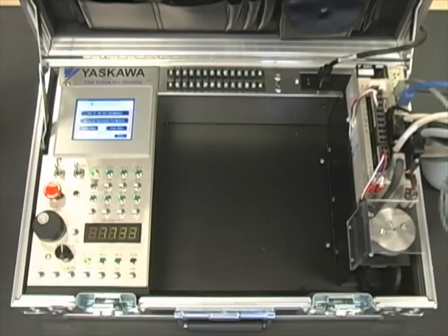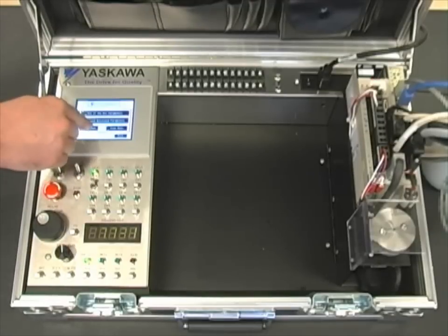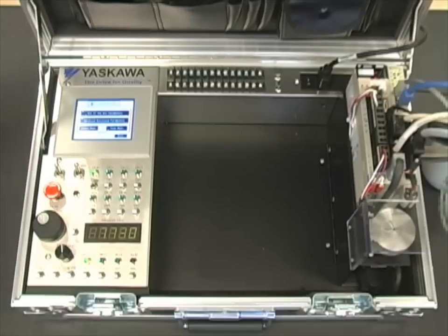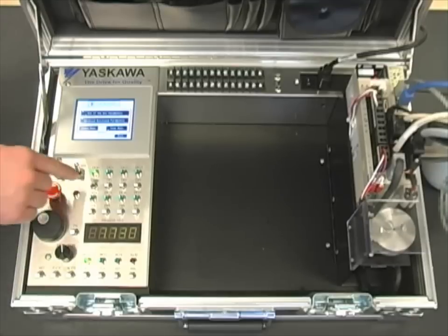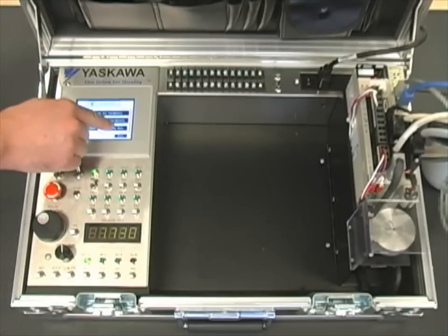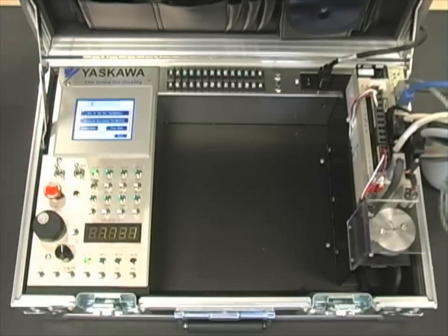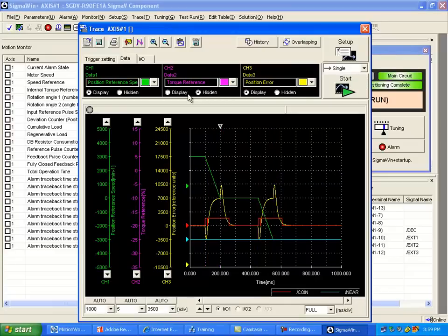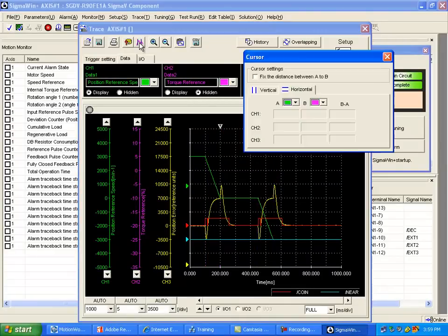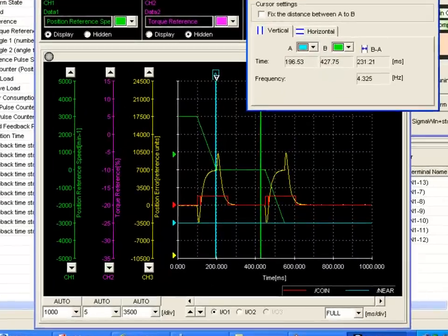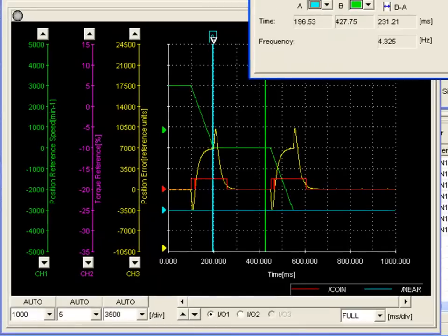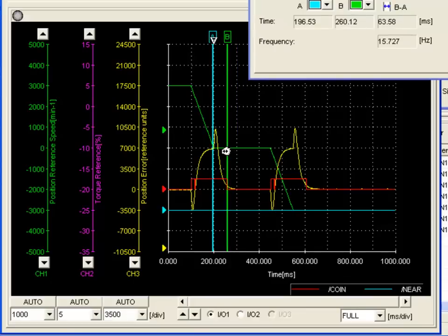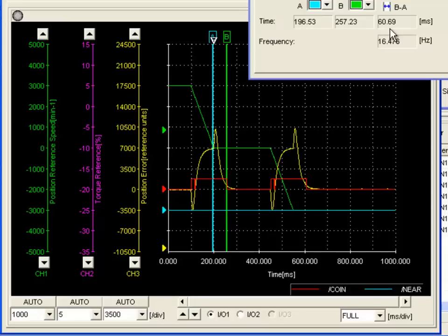Enable our servo and select Start Move. Now let's hide the torque reference signal again and bring up the cursors. We're going to leave the A channel where it was previously and move the B channel to the falling edge of the coin signal. As you can see, our settling time is reduced to around 61 milliseconds.